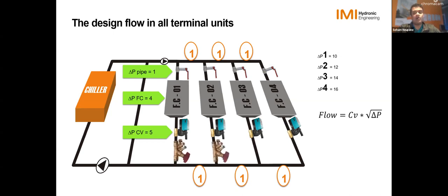So now we're gonna go and place some balancing valves in here. So once we do that, how do we select the right balancing valve, right? How do we know the resistance we need? So 1 feet of pressure drop is what you always want to design for in your index unit. So when I say index, that's the hardest to satisfy. And in this circuit, it's going to be your last one. So what we want to make sure is we have minimum pressure drop on this index unit, because if we size this for a higher pressure drop, we're going to have higher pressure drop in all of these valves upstream, and we'll look at why.